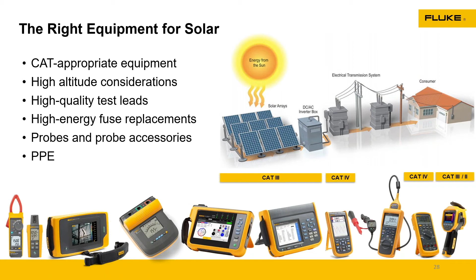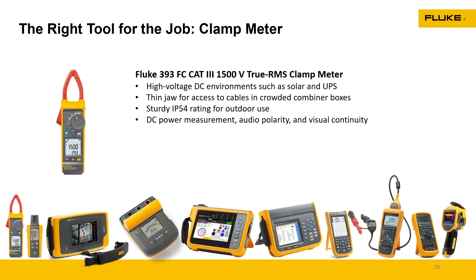So let's break down some of the tools that I mentioned earlier. A clamp meter is going to allow you to make your DC current measurements and your AC current measurements. This is going to help you again in every aspect of the solar system, whether that's your solar panels, your combiner boxes, or your inverters, even on doing load studies. Make sure that your meter is appropriate and maybe even needs an IP rating for outdoor environments. That IP rating determines how many particles can get into the meter and if it's waterproof. So we just want to make sure that's appropriate and know that the meter is going to be able to do DC power. You've got to have DC if we're talking solar. Some of those are the key wins to having the right clamp meter in this environment.